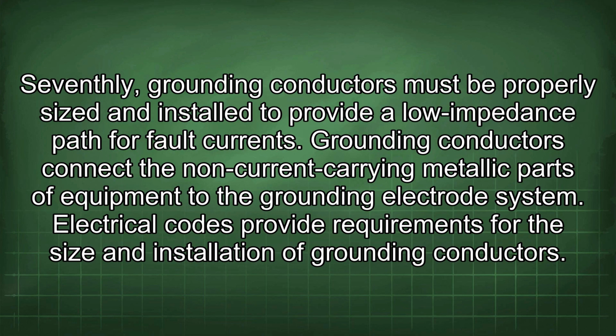Seventhly, grounding conductors must be properly sized and installed to provide a low impedance path for fault currents. Grounding conductors connect the non-current carrying metallic parts of equipment to the grounding electrode system. Electrical codes provide requirements for the size and installation of grounding conductors.